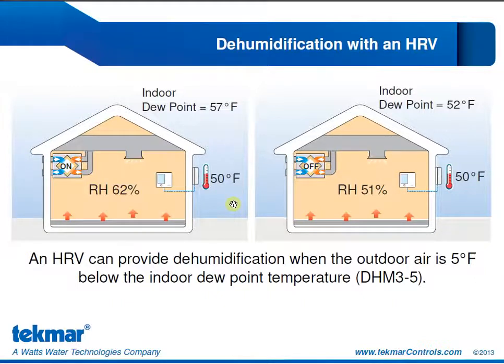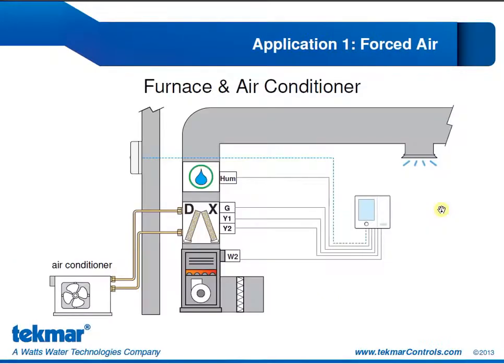Dehumidification with an HRV, as I said before, is possible if the outdoor air is at least 5 degrees below the indoor dew point. So the 557 will do the dew point temperature calculation based on the relative humidity of the room and based on the temperature of the room. And if the outdoor temperature is at least 5 degrees below that indoor dew point, the HRV can turn on. Once the outdoor temperature is 2 degrees below the indoor dew point, we're going to turn the HRV off. But you can notice that we have actually managed to decrease our relative humidity from 62% to 51% while that HRV was operating. So it is a very effective mode of dehumidification when conditions allow it to operate.